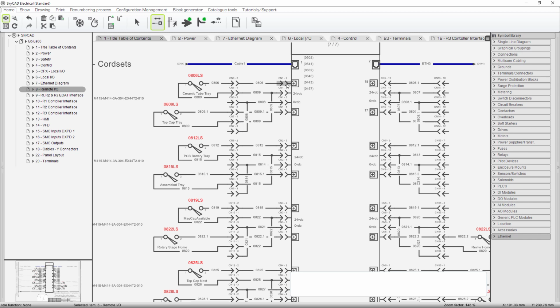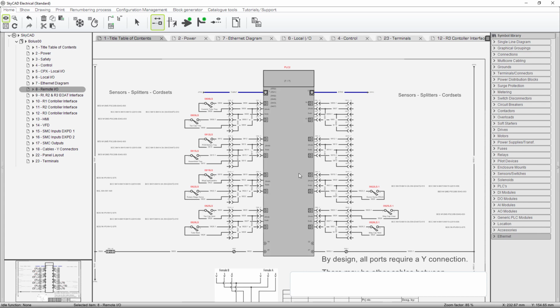This is your input right there. That's the input for that sensor. That's the input for that sensor. That's 2 wires. This wire and this wire both are 24 volts DC. So you can take this wire and this wire and put it inside of one screw terminal inside that field wireable connector. And then you can do the same thing with the commons. Okay, so this is remote I/O.